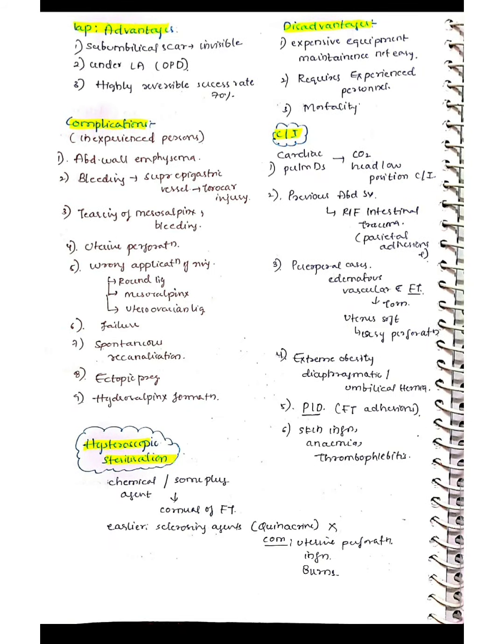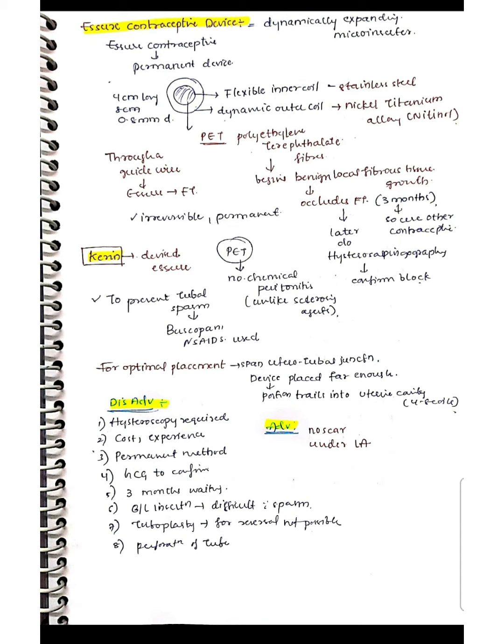The Essure contraceptive device is a hysteroscopic method of contraception. It is a dynamically expanding microinsert — a permanent device with a flexible inner coil made of stainless steel and a dynamic outer coil made of nickel titanium. The inner coil contains PET fibers (polyethylene terephthalate). When inserted into the cornual portion of the fallopian tube via hysteroscope, these PET fibers cause benign local fibrous tissue growth, which occludes the fallopian tube. This process takes approximately three months.